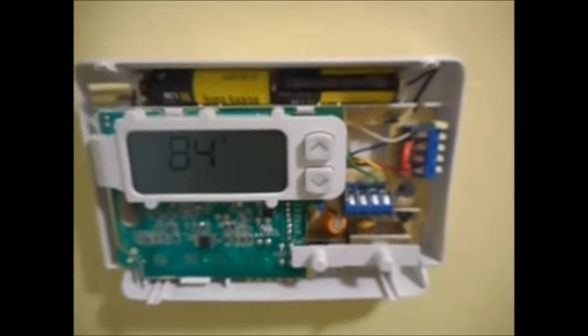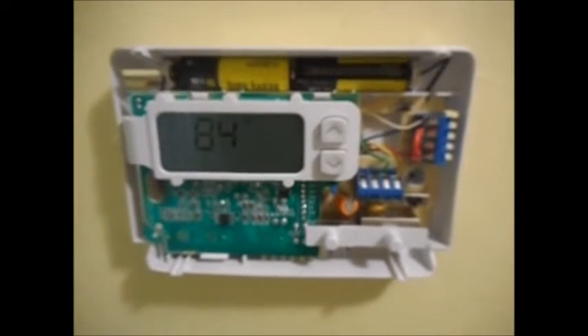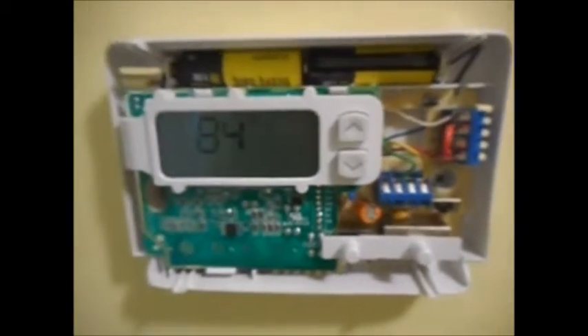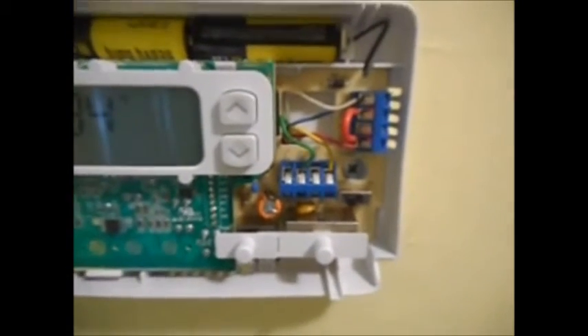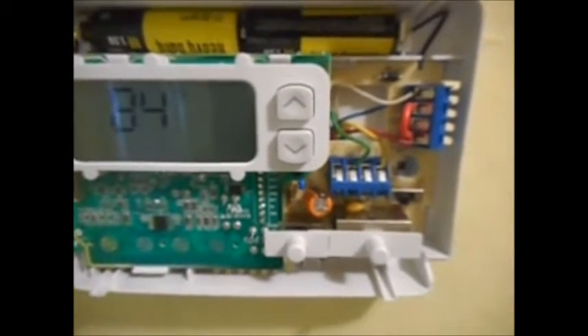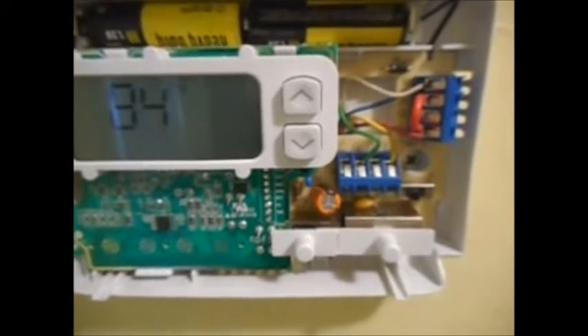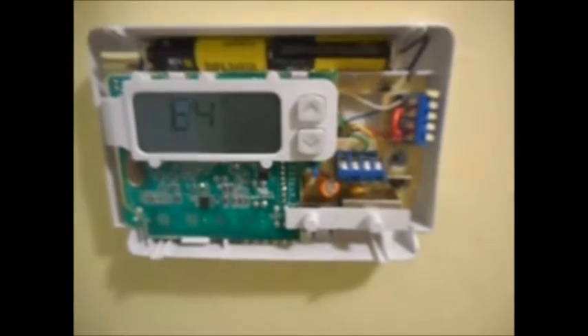All my wires are screwed in and tight, except for the blue one — the blue one is just coming out of the wall. The blue one is only needed if you don't have a battery-powered display; then you connect it to the B terminal. I want to thank Mr. Kuhl in Cape Coral for helping me with the wiring diagram and telling me the blue wire was only the source for the display, and that the red wire goes into the RC side of the jumpers. White to white, red to the RC, green to green, yellow to yellow, and the blue wire is not connected.